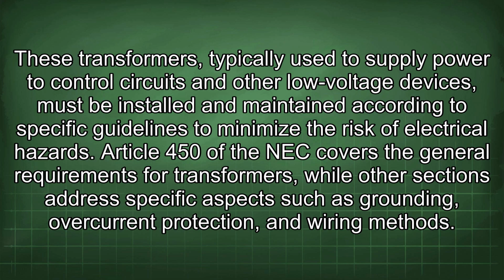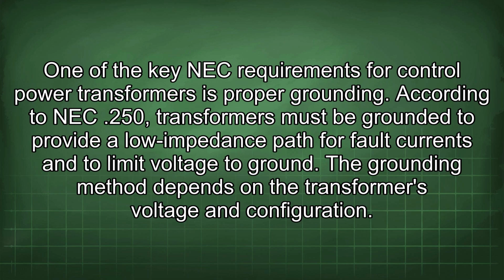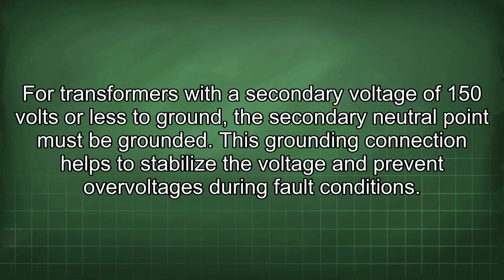Article 450 of the NEC covers the general requirements for transformers, while other sections address specific aspects such as grounding, overcurrent protection, and wiring methods. One of the key NEC requirements for control power transformers is proper grounding. According to NEC 250, transformers must be grounded to provide a low impedance path for fault currents and to limit voltage to ground. The grounding method depends on the transformer's voltage and configuration. For transformers with a secondary voltage of 150 volts or less to ground, the secondary neutral point must be grounded. This grounding connection helps to stabilize the voltage and prevent overvoltages during fault conditions.